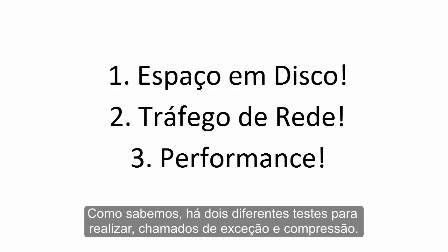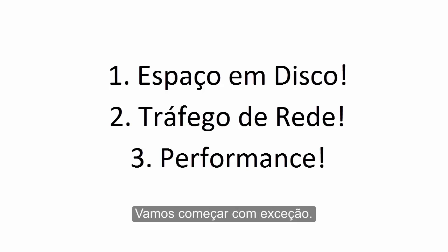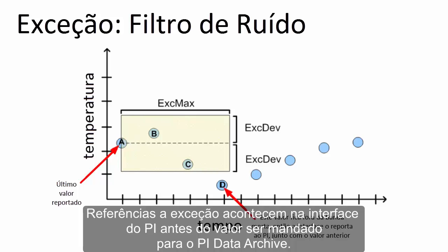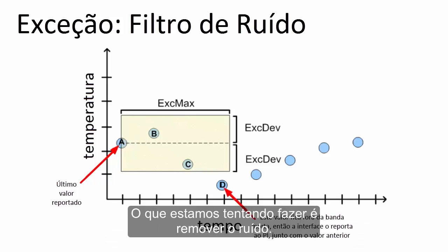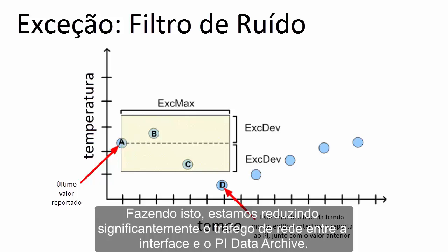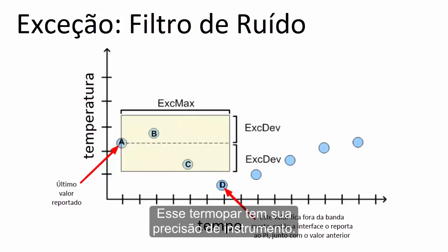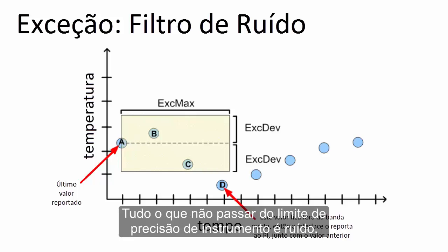There are two different tests which we perform, namely exception and compression. Exception reporting takes place on the PI Interface before the value is actually sent to the PI Data Archive. What we are trying to do is remove the noise, significantly reducing the network traffic between the PI Interface and the PI Data Archive. To understand this, consider a thermocouple monitoring temperature — this thermocouple has some instrument precision, where anything that falls within the instrument precision is really the noise.